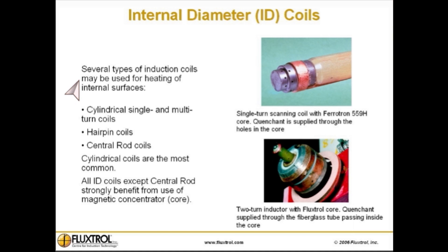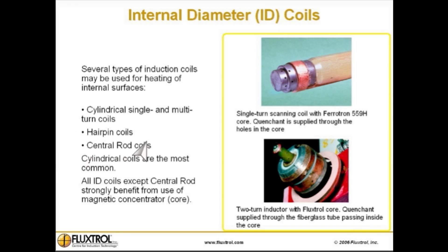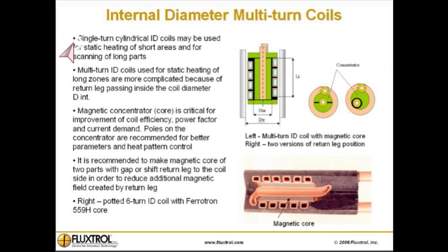Internal diameter coils: several types of induction coils may be used for heating of internal surfaces — cylindrical single and multi-turn coils, hairpin coils, and central rod coils. Cylindrical coils are the most common. All ID coils except central rod strongly benefit from use of a magnetic concentrator or core. Examples of single-turn and two-turn coils with magnetic cores are shown here.